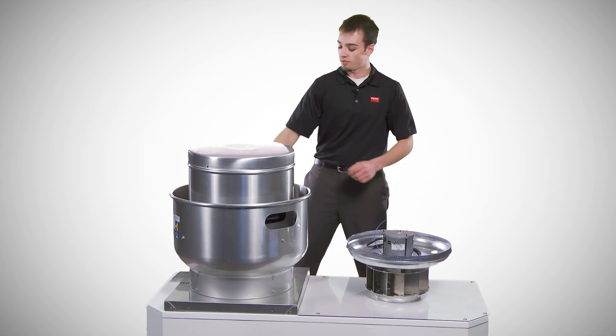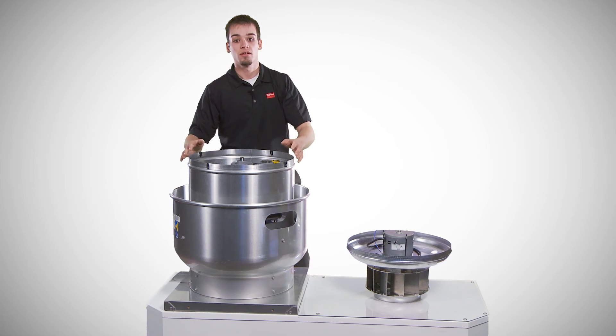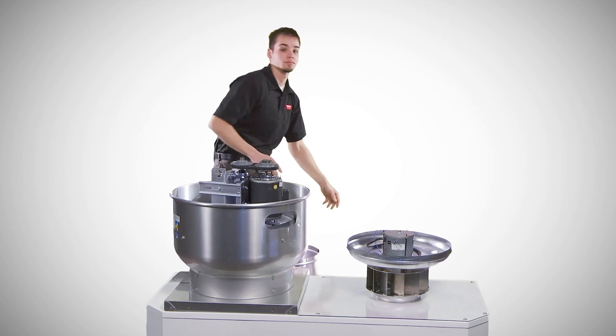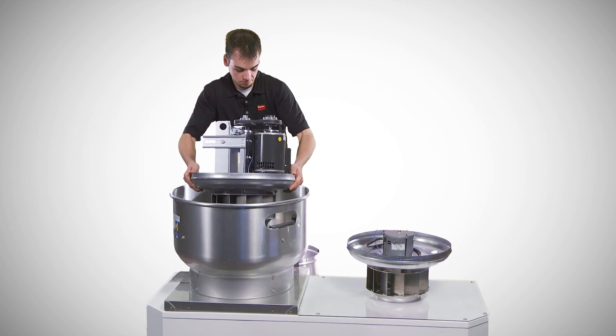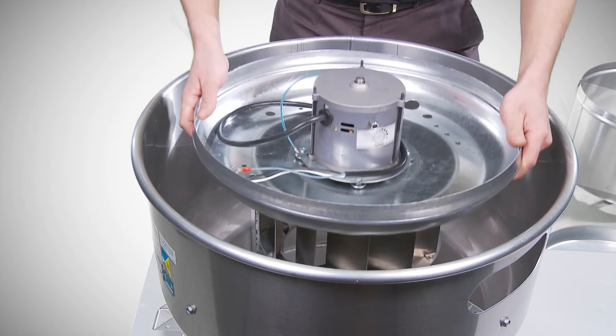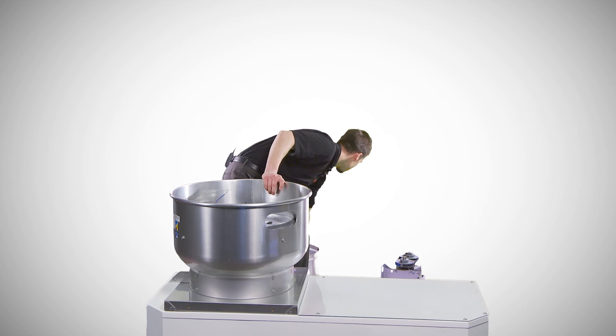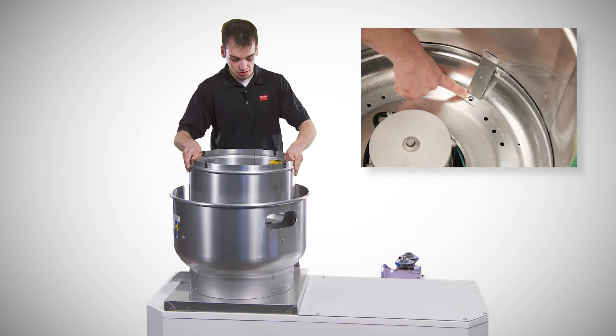First, remove the four screws from the motor cover. Then remove the four screws on the support pan. Next, remove the wind band. Take the existing drive assembly out — you will no longer need any of this assembly. Put the new power pack in place, lining up the mounting holes. Put the wind band in place. And reinsert the screws into the support pan.